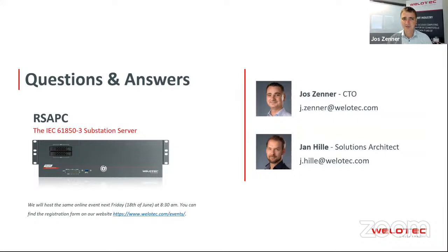There is, I was talking to ETAP recently. They have one of those solutions. So converting protocols is not a problem. They can run on our platform without any issue. Usually you speak IEC 61850 within the substation, and then you go northbound with DNP3, or in Europe you would take IEC 104.